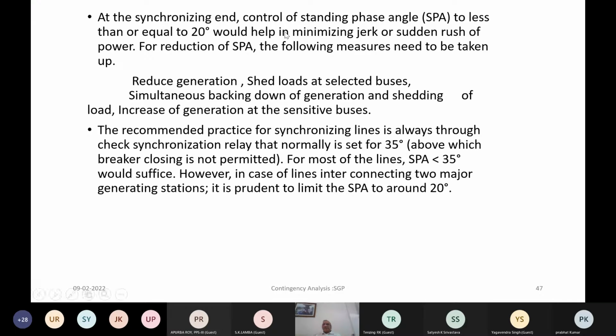At the synchronizing end, control of standing phase angle to be less than or equal to 20 degrees. That means to avoid jerk, heavy power surge at the moment of synchronizing, to keep it to the minimum, otherwise system may collapse again because you are already in the isolated grid mode and only a black start generator is feeding the area. So the angular difference should be kept under control, and the guideline is it should be within 20 degrees.